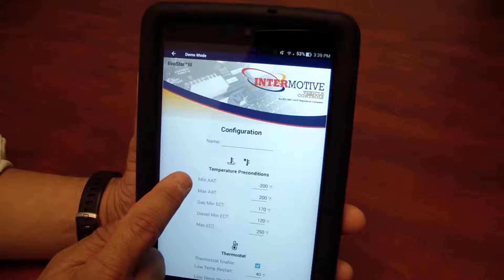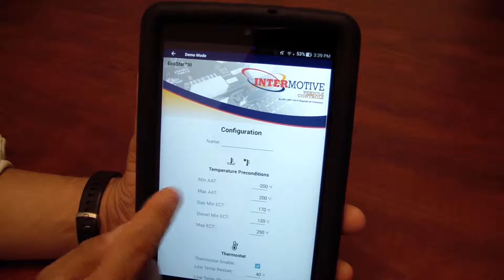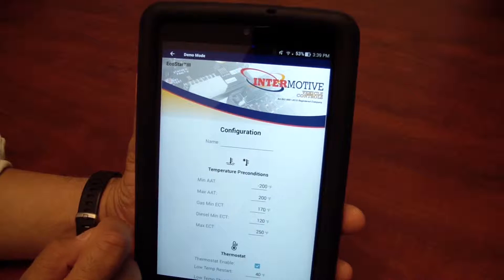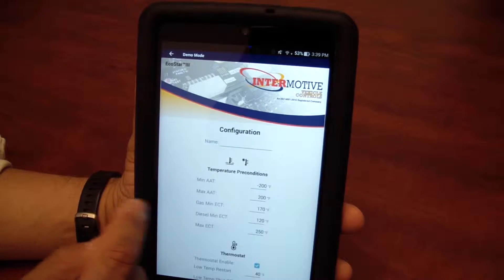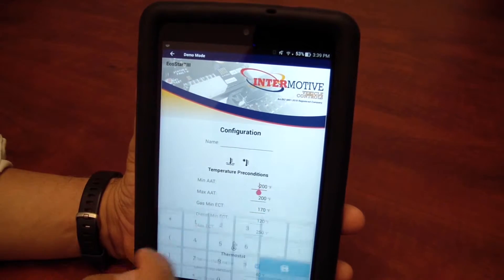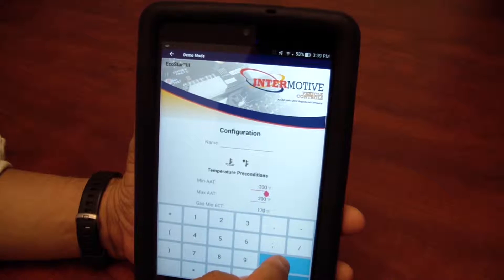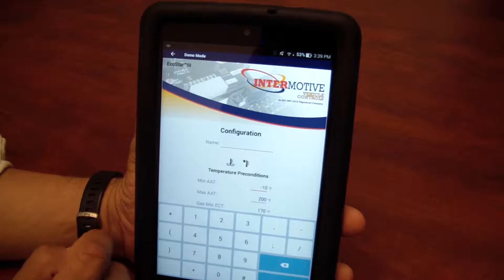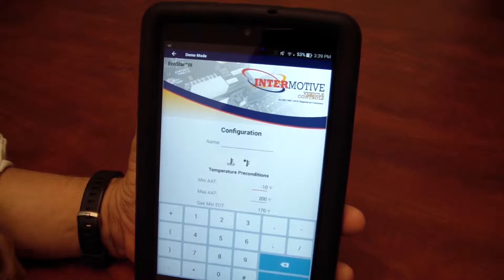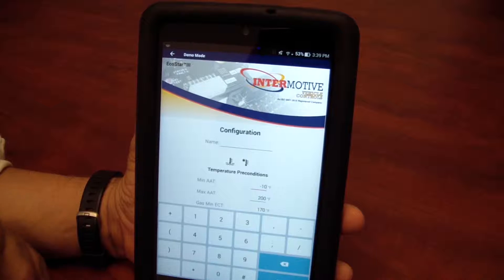We have minimum ambient air temperature and maximum ambient air temperature. Why would you use those? Say if the temperature outside is minus 10 degrees or colder, we may decide we don't want EcoStar to go active — it's just too cold.